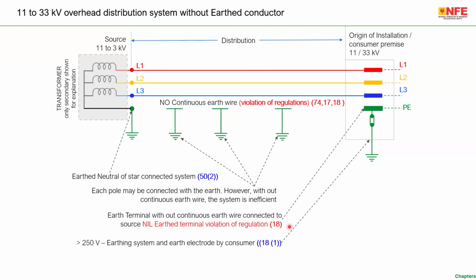So under this condition, what happens is the terminal at the consumer premise, let's say an 11 kV consumer, you cannot call this an earthed terminal. You can call this terminal an earthed terminal only if there is a continuous earth wire. Now there is no earth wire. You are just having an earth electrode and connecting. Under this condition, this is a violation of this earth terminal. This terminal is a violation of regulation 18.